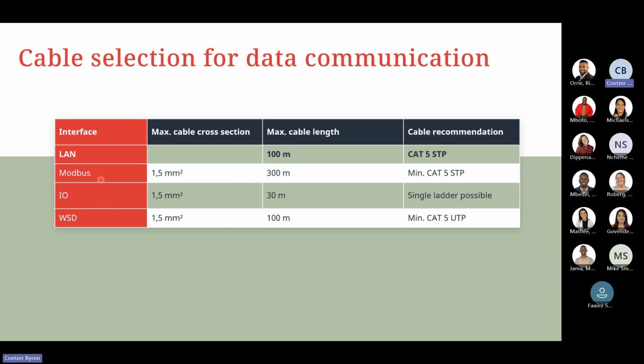Lastly is just your cable connection for the data communication side. In the LAN connections, we have a maximum of 100 meters from the device to the router or switch that you're using in the system, with Cat5 STP or UTP cable and above. So we always recommend using Cat5 or Cat6. It doesn't need to be anything fancy like Cat7, for example. Just normal Cat5 is more than sufficient on the LAN connection side.